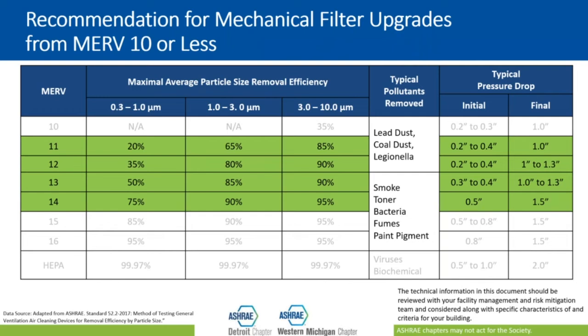They can get these in low drop models, and they also tend to be more available, right? Because everybody's looking for better filters right now. So the cost of the filters has gone up, and it would have gone up anyway because higher MERV filters are more expensive. For example, a 24 by 24, 12-inch HEPA filter might cost $500. If you were to get a 24 by 24 1-inch filter, that's $10, right? $15. So a significant price increase. And on top of that, the availability, right? Because everybody is demanding these filters. So lead times are out the wazoo, right? They're just not acceptable for most applications.